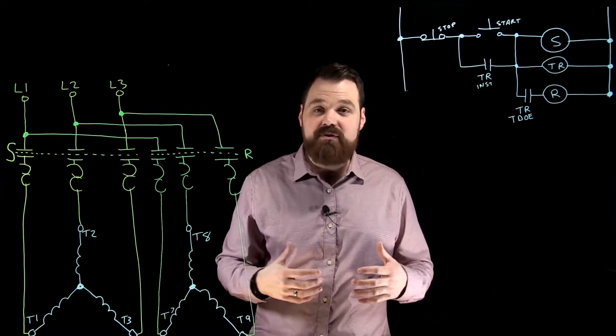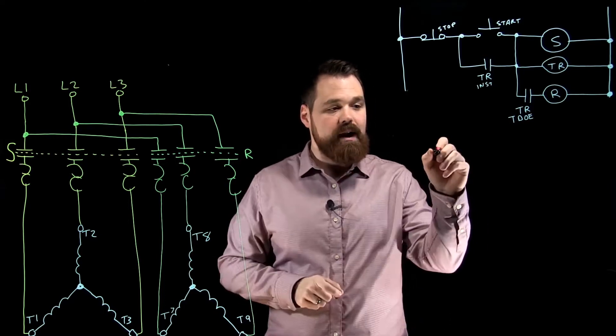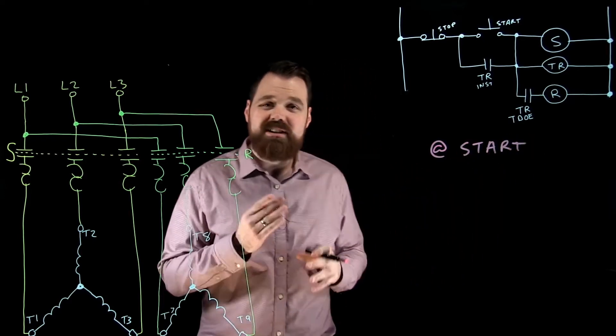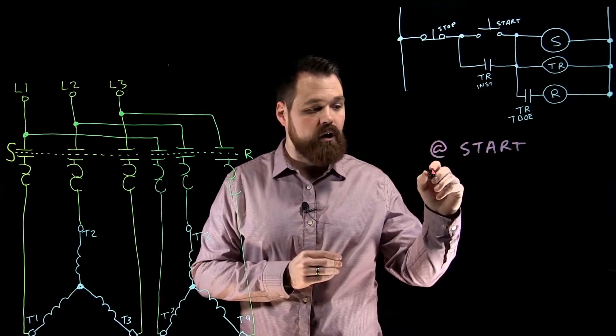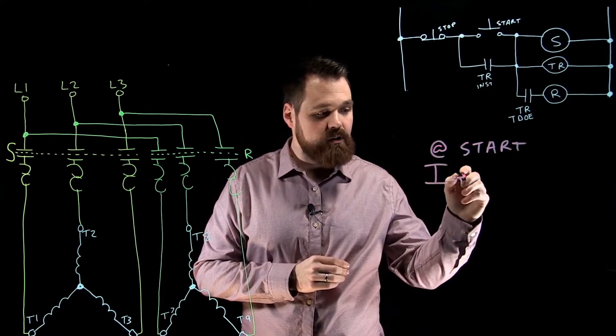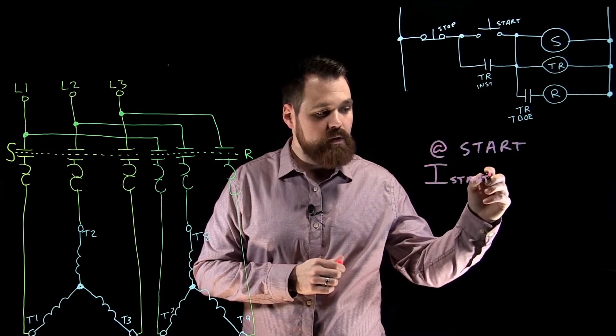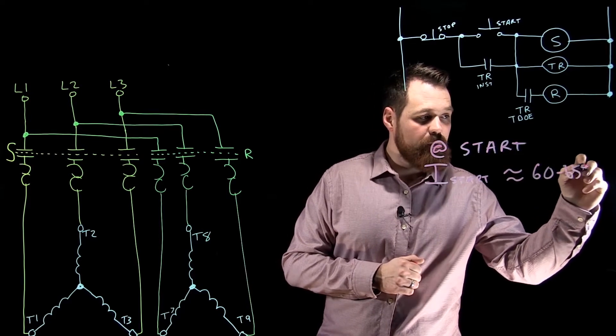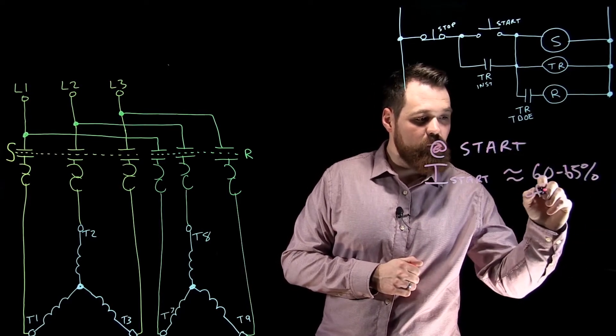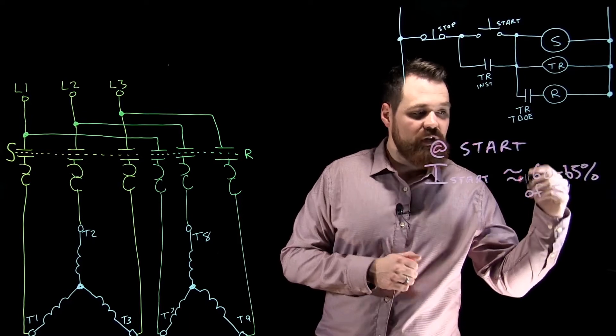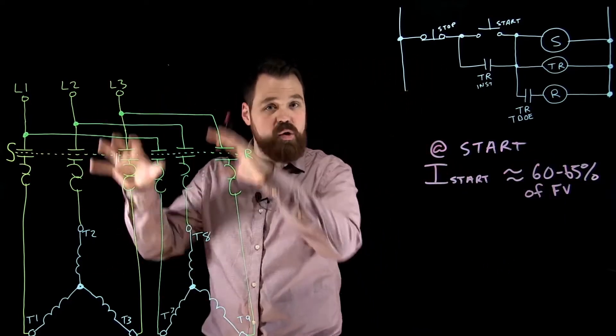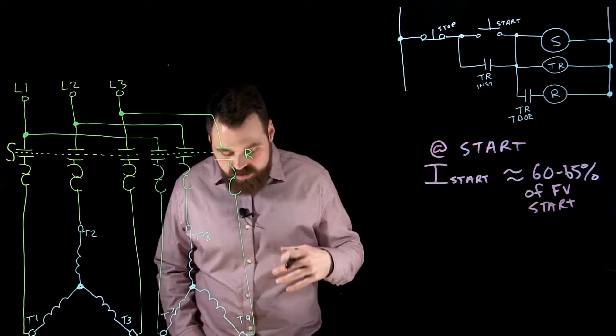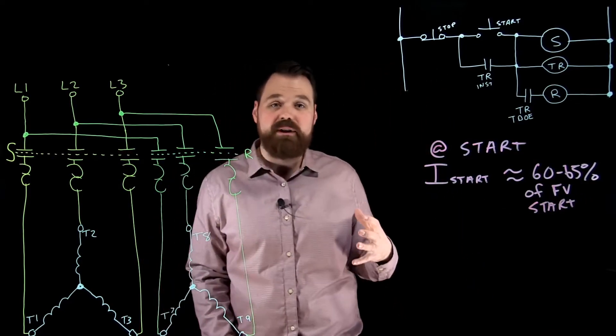So what this gives us at start is our current, our I at start, is approximately 60 to 65% of what it would be at full voltage if you were to just start this motor with both windings at the same time, full voltage start. So we can see that great reduction in current, which is really good for us.